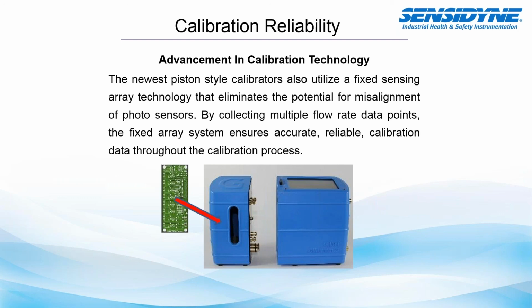Some additional advancements include fixed sensing arrays. As I mentioned earlier, older technology would have a top and bottom optical sensor. However, by having a fixed sensing array, there's no chance of those sensors becoming misaligned, and you can actually collect more data points along a fixed sensor array than you can with just a top and bottom optical sensor. And as you can imagine, having more flow rate data points ensures both accurate, reliable calibration throughout that calibration process.